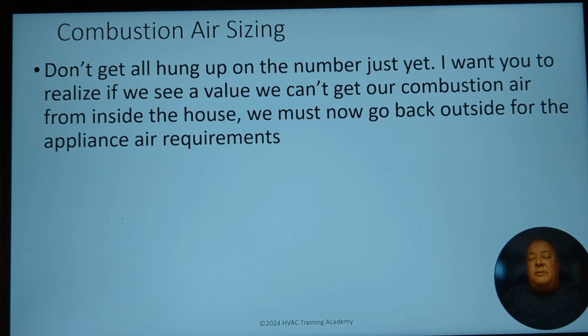Don't get hung up on the number. I want you to realize when you see the value, we can't get our combustion air from inside the house, so now we have to go back outside for appliance air requirements. And I'll tell you the reason why I tell you not to get held up on the number. A lot of technicians, as soon as they see that number, think that if I cut a hole in the wall that's 18 inches square, I've satisfied the requirements to get the air to my appliances.